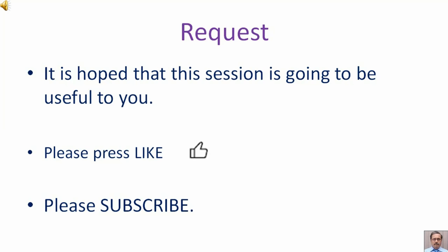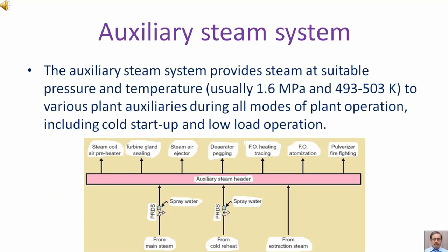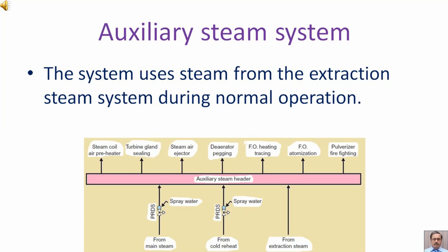The auxiliary steam system provides steam at suitable pressure and temperature to various plant auxiliaries during all modes of plant operation, including cold start-up and low load operation. The auxiliary steam pressure is usually 1.6 mega Pascal and temperature is between 493 to 503 degree Kelvin.